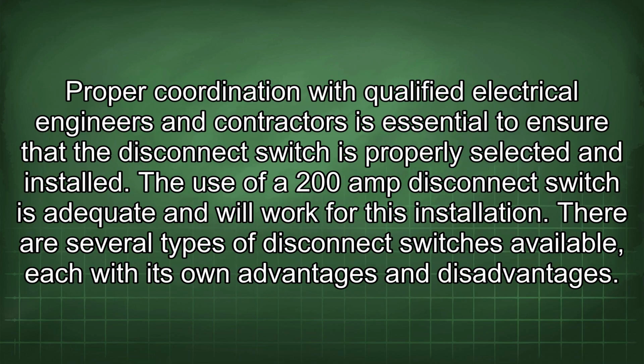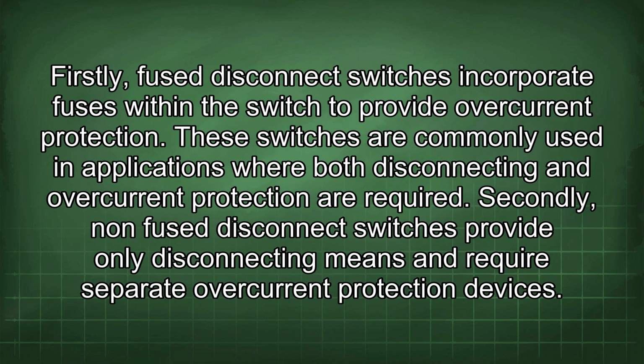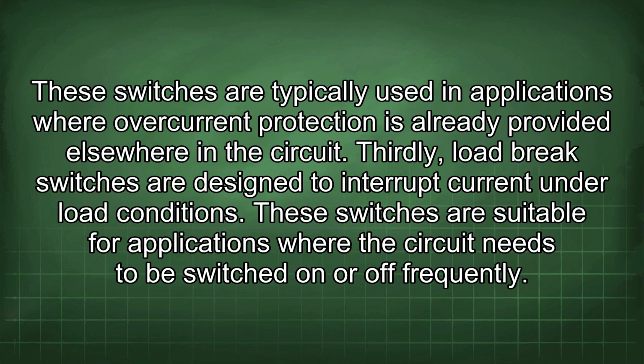Proper coordination with qualified electrical engineers and contractors is essential to ensure that the disconnect switch is properly selected and installed. The use of a 200 amp disconnect switch is adequate and will work for this installation. There are several types of disconnect switches available, each with its own advantages and disadvantages. Firstly, fused disconnect switches incorporate fuses within the switch to provide overcurrent protection. These switches are commonly used in applications where both disconnecting and overcurrent protection are required. Secondly, non-fused disconnect switches provide only disconnecting means and require separate overcurrent protection devices. These switches are typically used in applications where overcurrent protection is already provided elsewhere in the circuit.